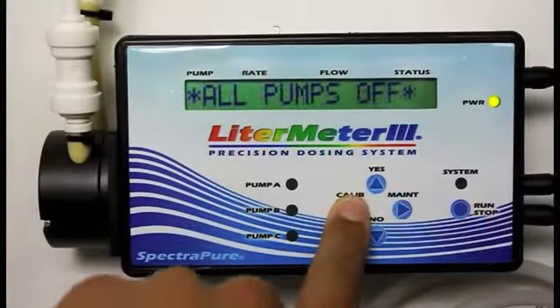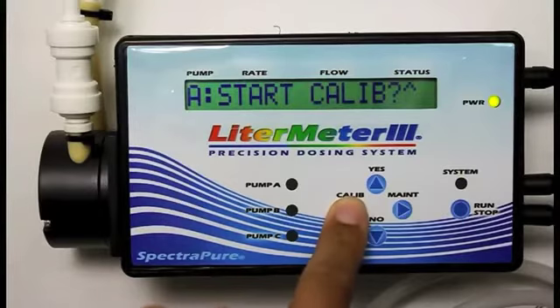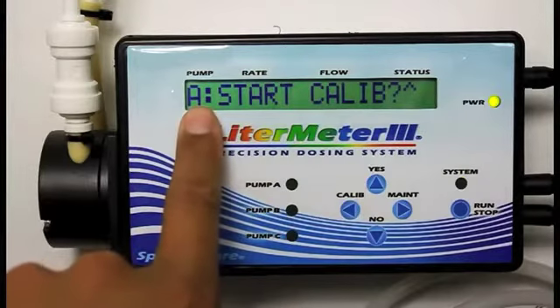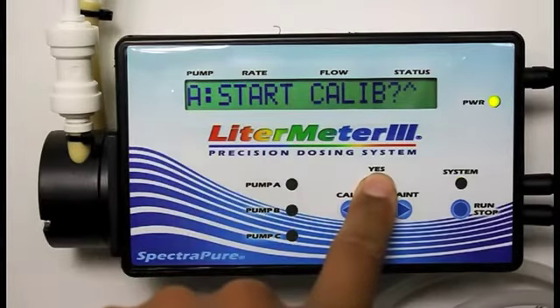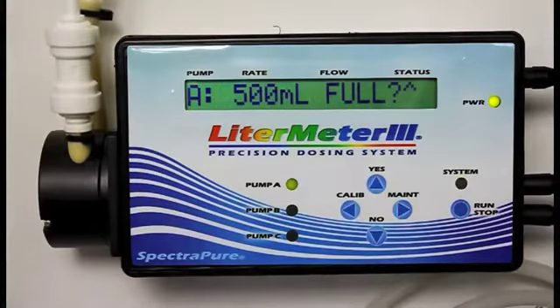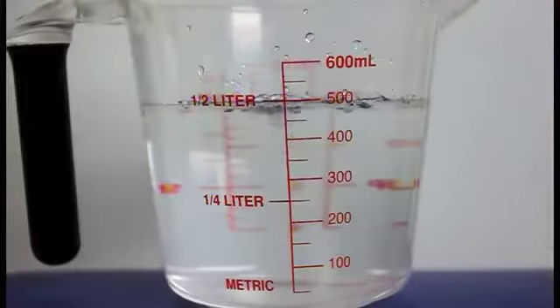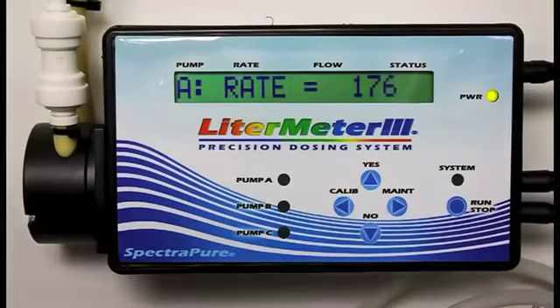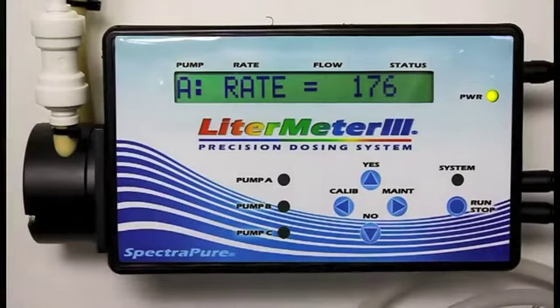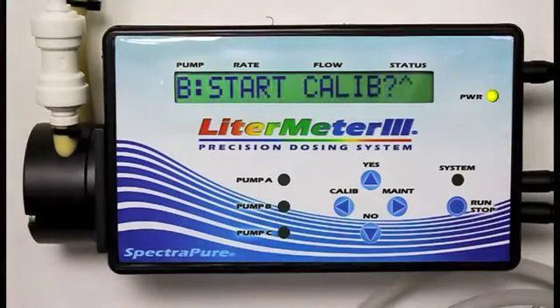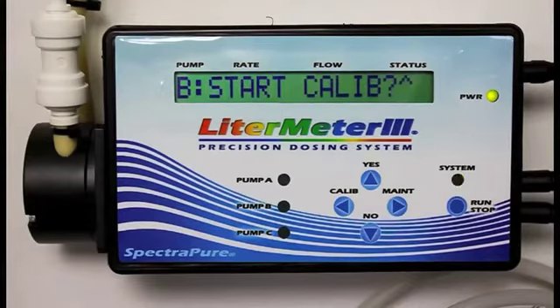Press the Run Stop button, then press the Calibration button and confirm the pump you want to calibrate. Direct the tubing to the measuring cup and press Yes to begin. The pump will now operate and dispense into the cup, asking you to tell it when you've collected 500 milliliters. Hit Yes when this is done. The pump briefly displays the maximum delivery rate and will automatically proceed to the calibration for the next pump, so repeat as necessary. If there are no additional pumps, just hit No. The system will return to all pumps off.